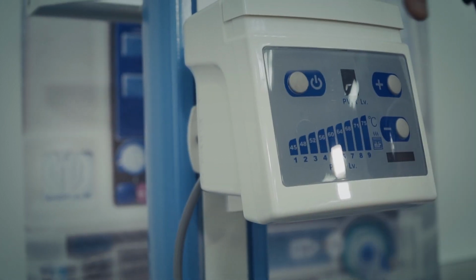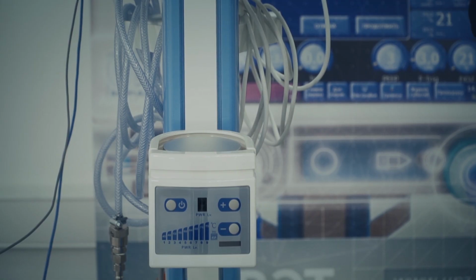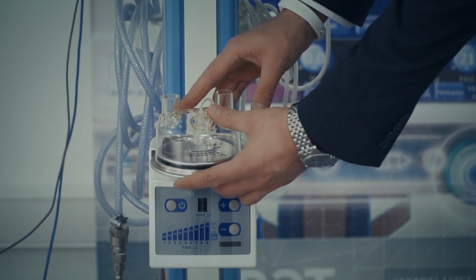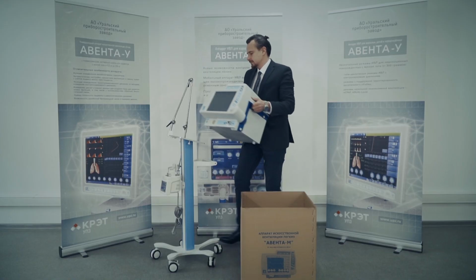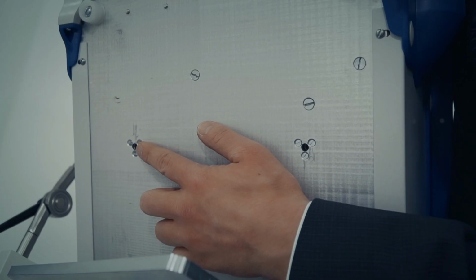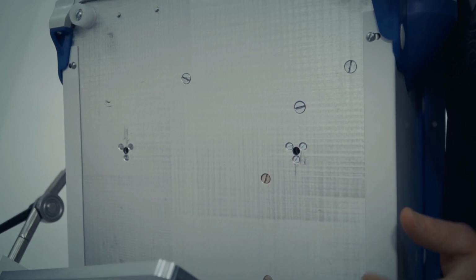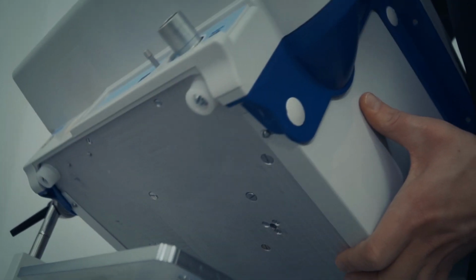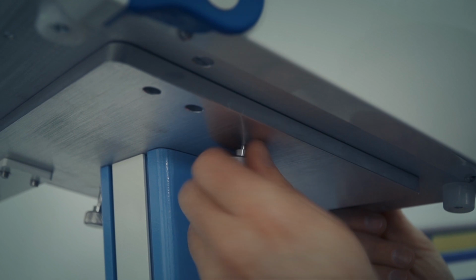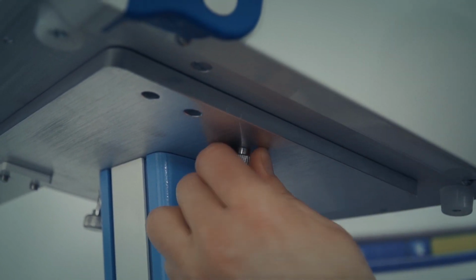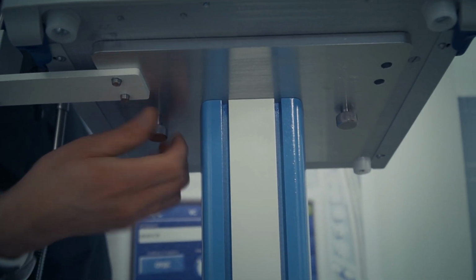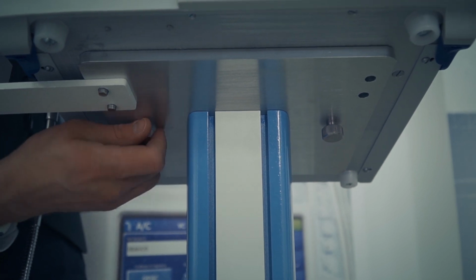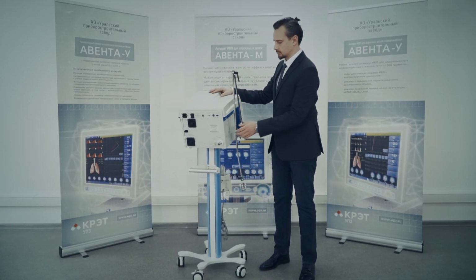Fit respiratory humidifier into a special slot on the front surface of the mobile trolley. Install humidifier chamber on the heated platform. Install lung ventilator body on the platform, making sure that holes on the bottom surface of the ventilator match with projecting screws. Tighten the screws to ensure secure fastening of the lung ventilator on the mobile trolley.